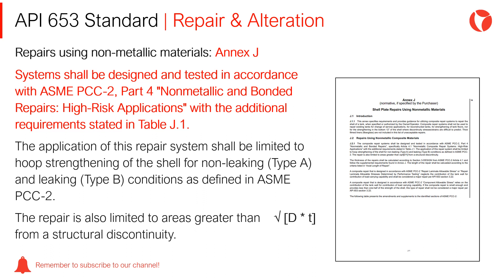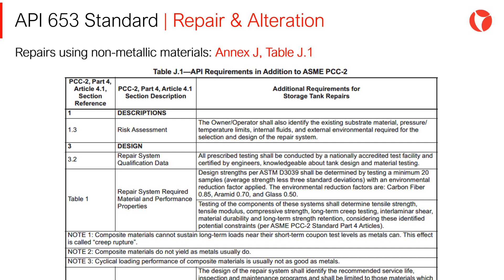The application of this repair system shall be limited to hoop strengthening of the shell for the non-leaking type A and leaking type B conditions as defined in ASME PCC-2. The requirements shown on Table J1 of Annex J should be added to those indicated in ASME PCC-2 in order to perform a repair with non-metallic materials.